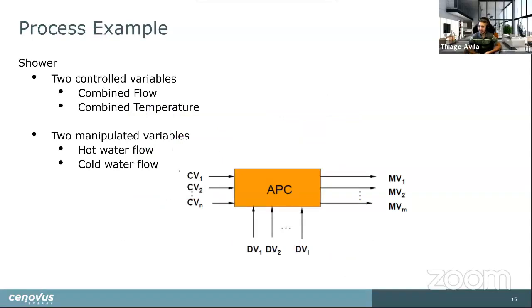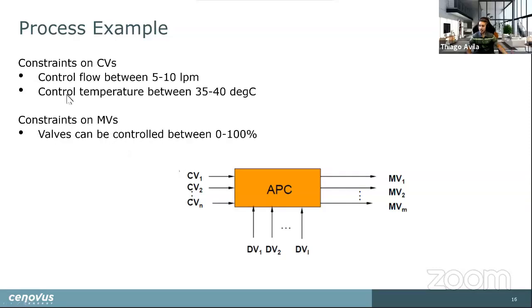And what the step testing might look like if you had two manipulated variables and then two controlled variables, you would do a bunch of different steps on MV1 and MV2. You'd be testing for interaction between these two. And by doing both of them in different amounts and in different ratios of the two, you'll be able to isolate what the independent impacts are of each one of these two manipulated variables. It'll also tell you whether your expected models are going to be linear over time. You could get a much different reaction between MV1 and CV1 at the high end of the range versus the low end of the range.